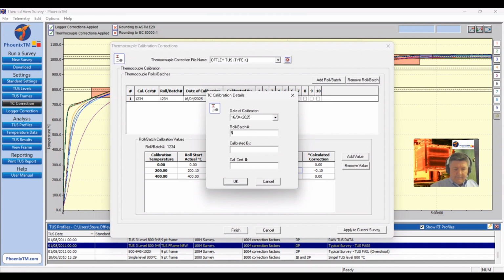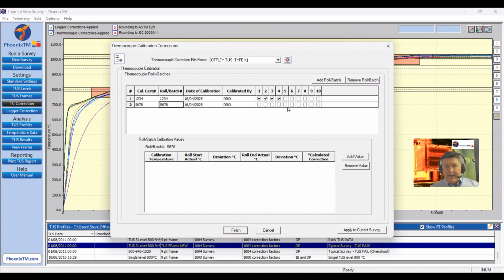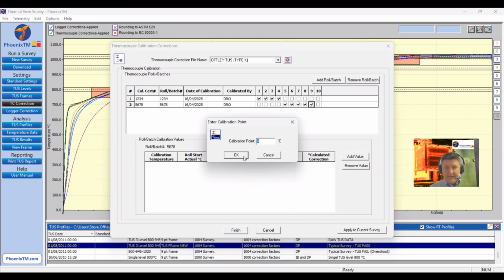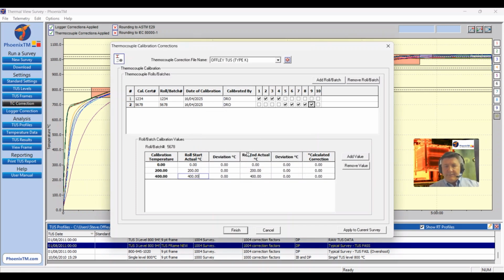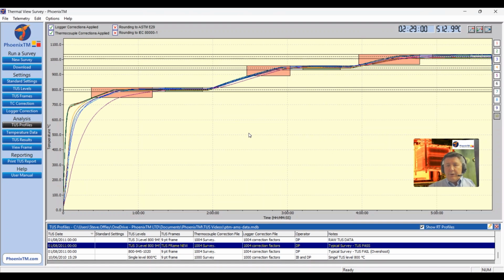So in this case, it's going to be 5, 6, 7, 8. Again, calibrated by myself. 5, 6, 7, 8. Okay, and in this case, I'm going to have thermocouples 5, 6, 7, 8, and 9. And in this case, I'm going to again add 0. Second calibration point is 200. 400. Okay, so I would again put in the actual roll start and the roll end actual values from the calibration certificate, basically transposing the data from the certificate itself to the software, and then it would automatically do the calculation. Once I've finished, I simply press finish, and that will now save that correction factor file in the software.